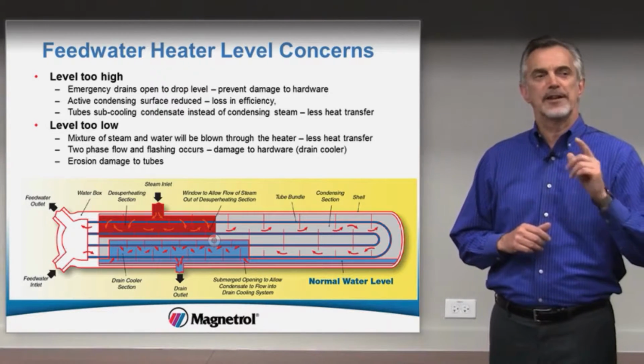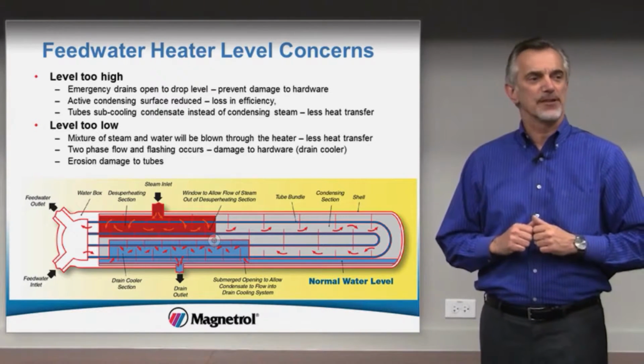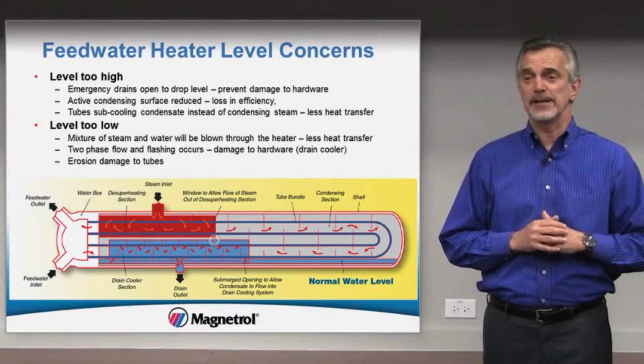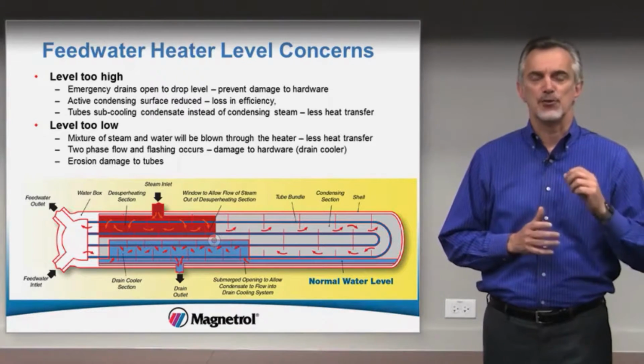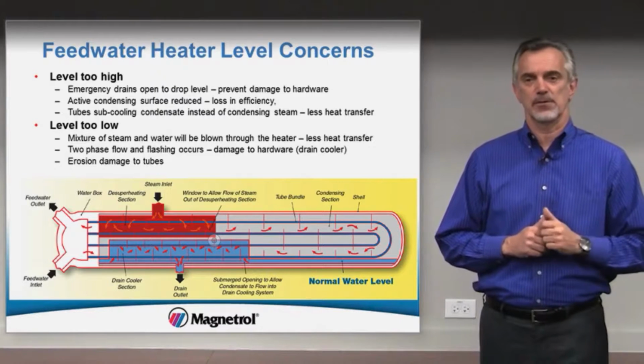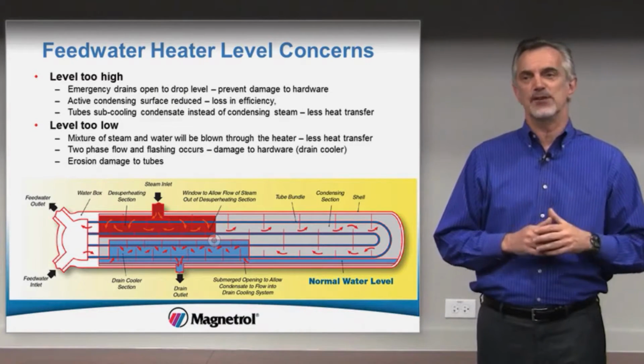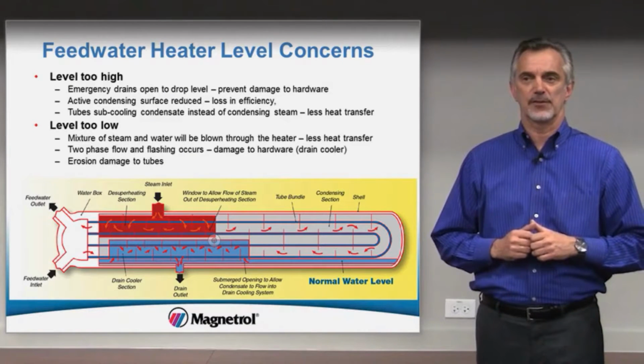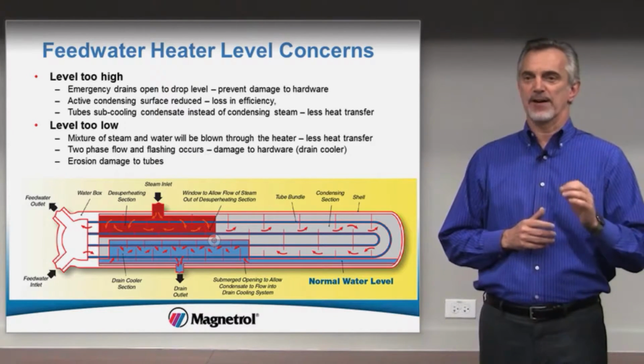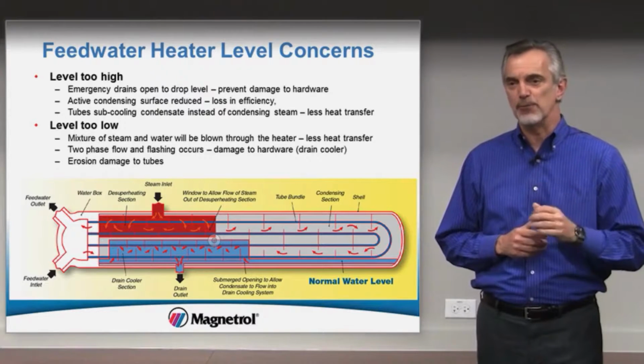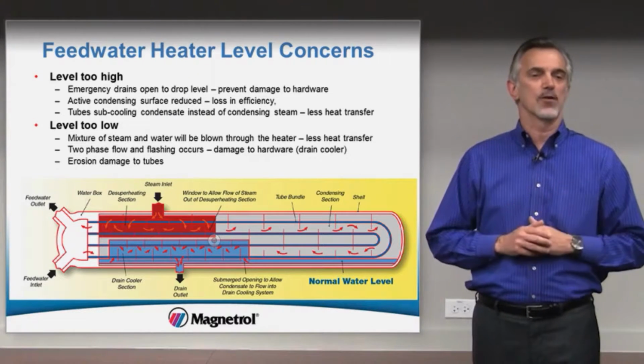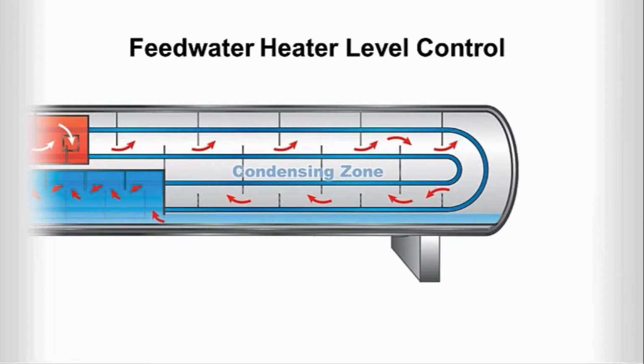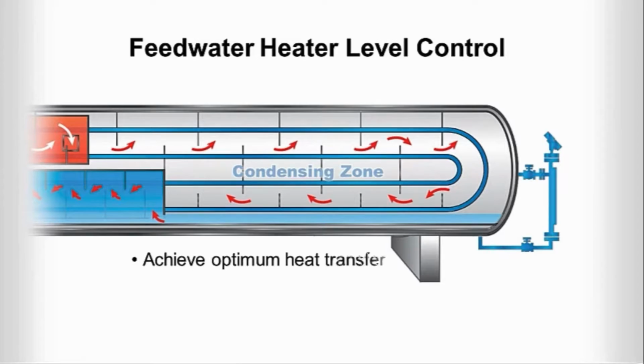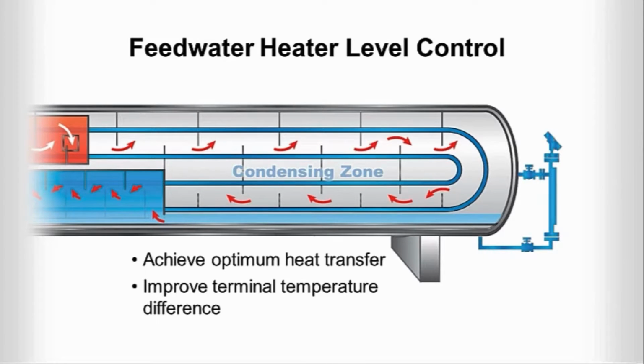Precision control of the feedwater heater during base load and cycling operations provides operators with the high degree of data certainty necessary to optimize the feedwater heater condensing zone. This is important for improved heat transfer during the condensation process. This will have a profound impact on the final feedwater heater temperature and ultimately heat rate, all without jeopardizing expensive hardware. There are normally 6 to 7 stages of feedwater heating. Making an investment in level control can help you achieve optimum heat transfer and improve terminal temperature difference to provide a significant return on investment.